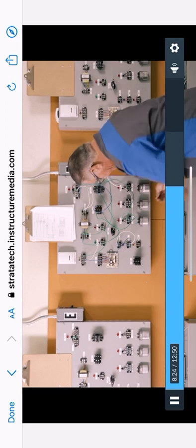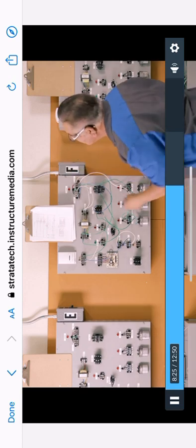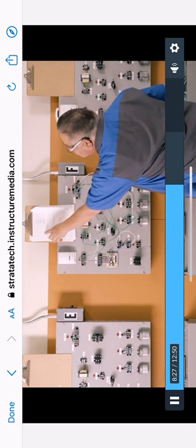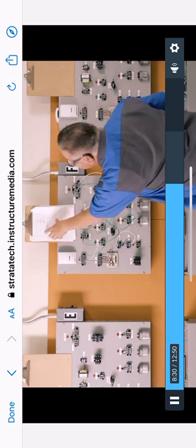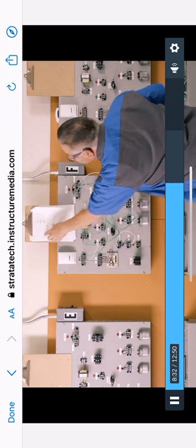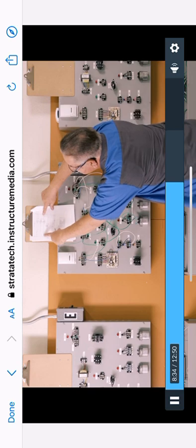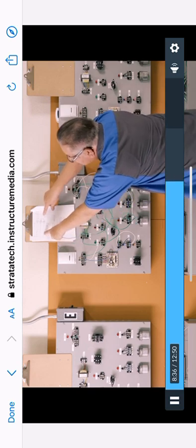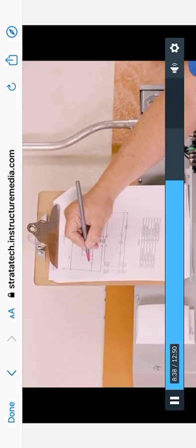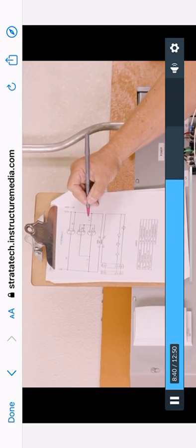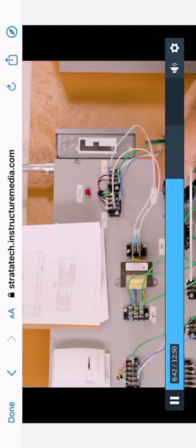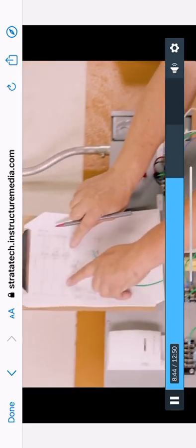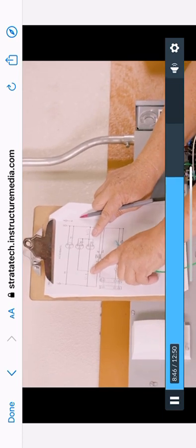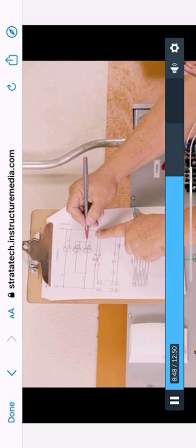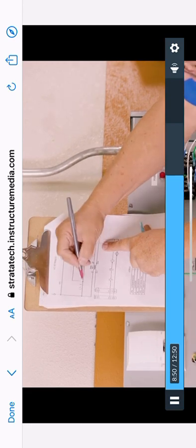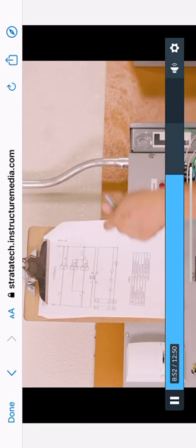I'm going to grab a wire. I'm going to go from line 1 to one side of my contactor, which is the top. This up here is the top of your contactor. This right here is line 1. This up here is line 2. That's the top right here. These on the inside of the C, where you see the C, that is your bottom. That is T2, and that is T1.